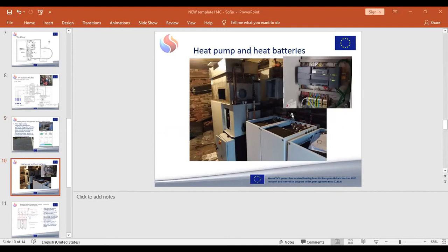As I mentioned before, the main characteristics of the hot water preheating system are heat batteries connected three in series, heat pump and domestic hot water circuits, and the command system, no balancing valves. Charging of the heat battery is controlled by a Siemens PLC, managing the circulation pump based on data from temperature sensors in the heat batteries. In the pictures here, on the right, you can see the basement heat pump, and a photo of the controller.